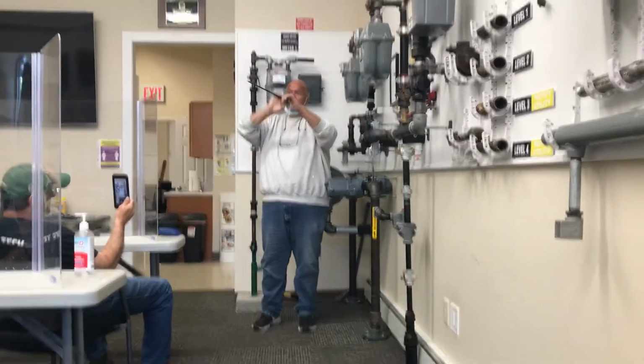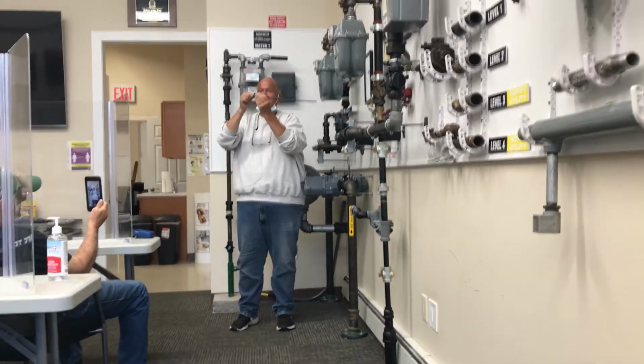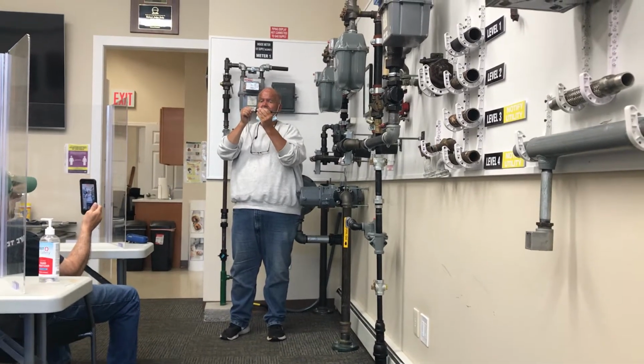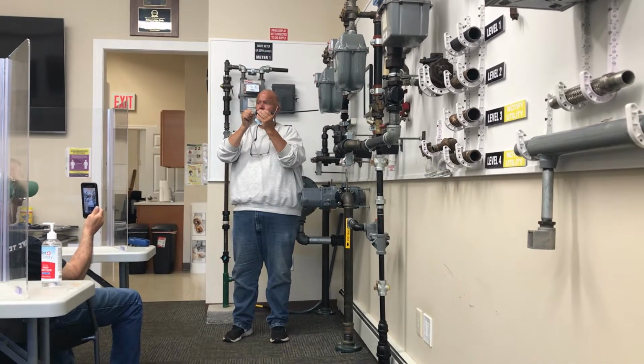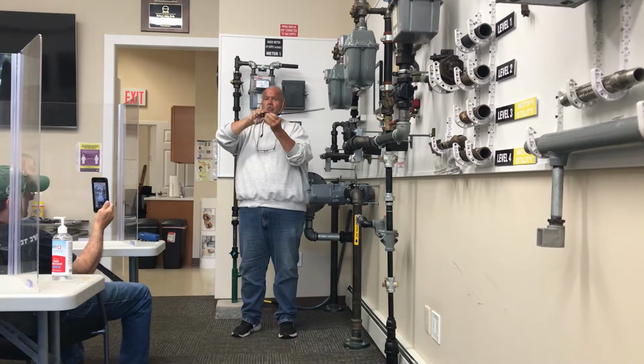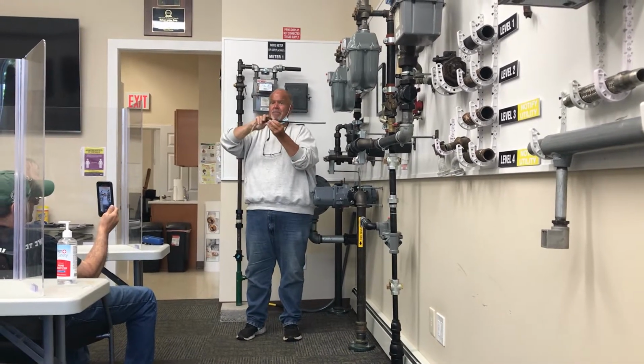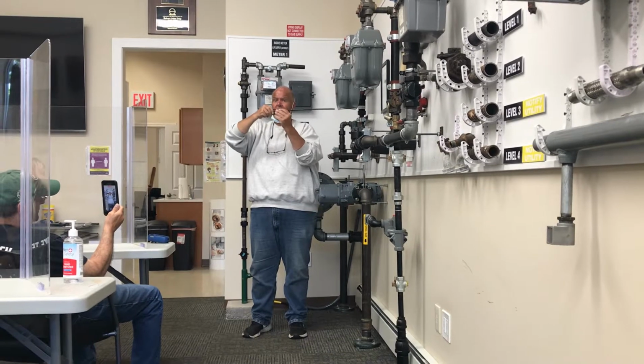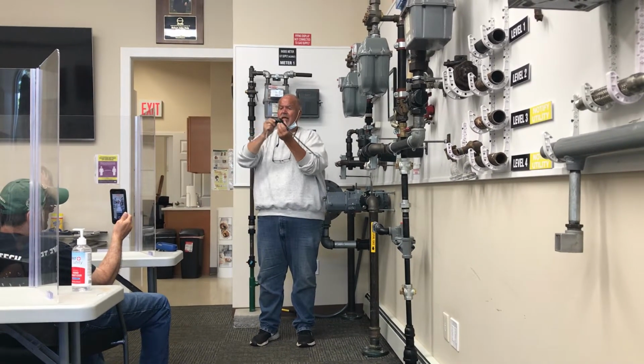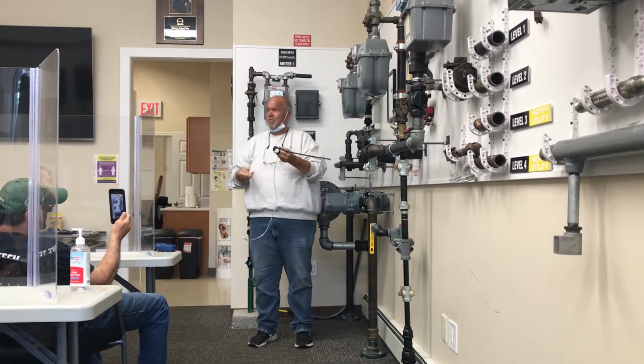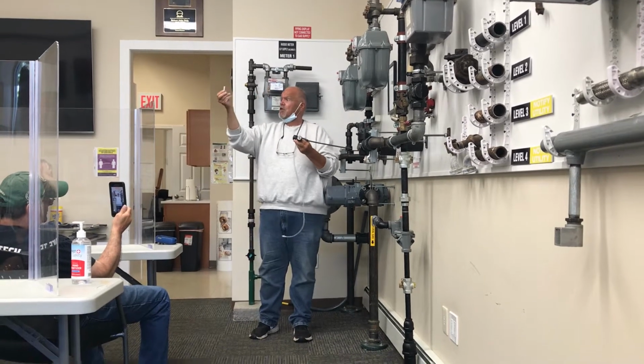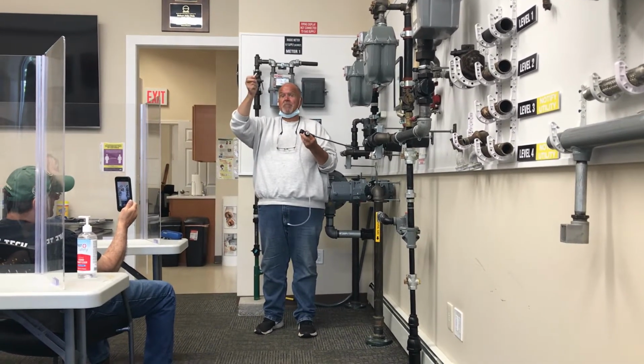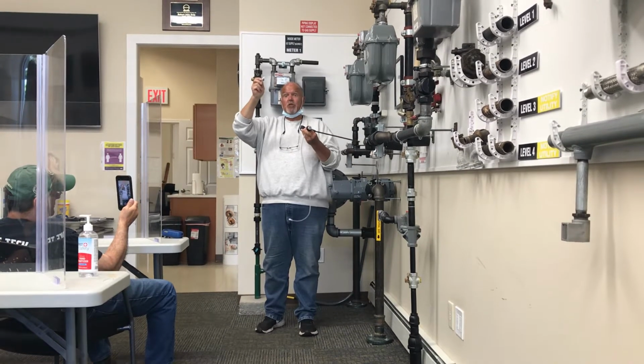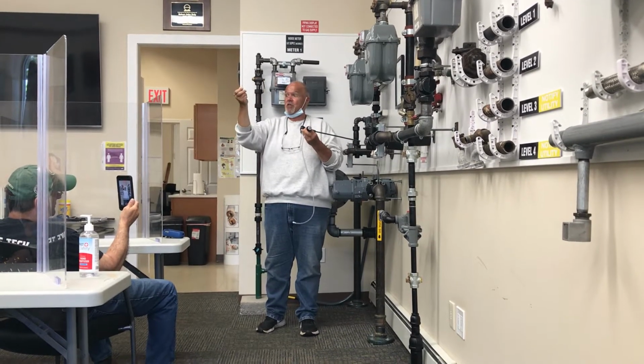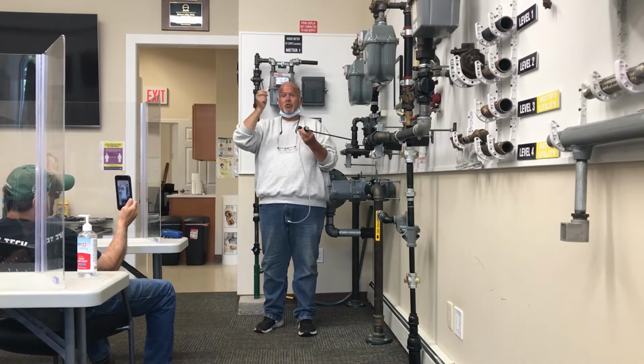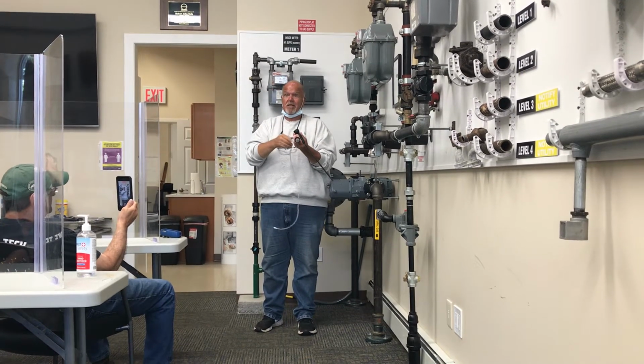At the other end of the probe handle, where the tubing connects, there's a stab connection. Check that, make sure it's nice and tight, it's not loose or cracked. Unscrew that cap in the probe handle, the wide end cap where the tubing connects. Inside are 2 filters. The first one is a dust or debris filter. It's designed to capture solids. It will capture moisture as well, but it's really designed for solids. It looks like a cigarette filter. You check it, it looks clean and dry, it looks okay, you can drop it right back in.